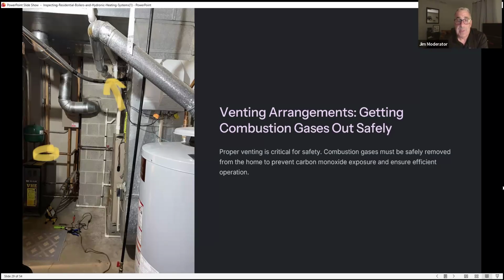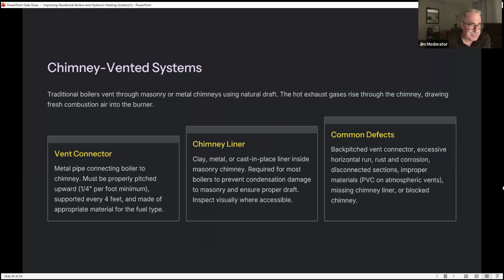Okay, so venting arrangements, getting combustion gases out safely. Proper venting is critical for safety. Combustion gases must be removed from the home to prevent carbon monoxide exposure and ensure efficient operation. Chimney venting systems: traditional boilers vent through masonry or metal chimneys using natural draft. The hot exhaust gases rise through the chimney, drawing fresh combustion air into the burner.